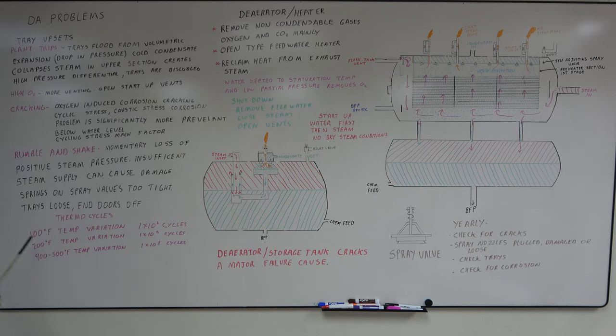Thermal cycles. 100 degree temperature variation on the deaerator, you can take a million cycles before you start having cracking. 200 degree temperature variation, 100,000 cycles before you start getting cracking. 400 to 500 degrees temperature variation, you can have 10,000 cycles before you start getting cracking.